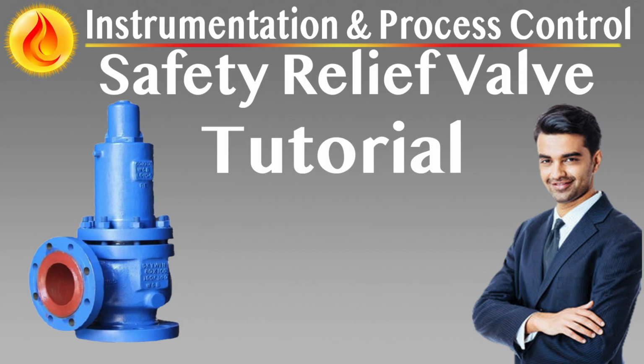Summary: balance type relief valves offer enhanced performance in systems subject to high or variable back pressure. By neutralizing the effects of downstream pressure on valve operation, they provide more reliable and predictable relief behavior than non-balanced types. However, their successful application depends on careful attention to vent routing, bellows material compatibility, and service conditions that could degrade or obstruct the balancing mechanism.